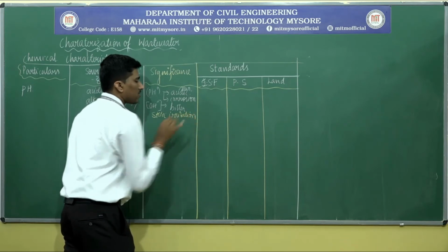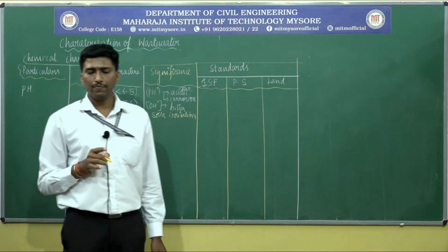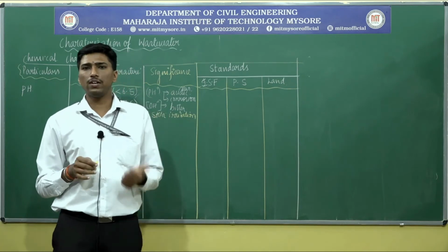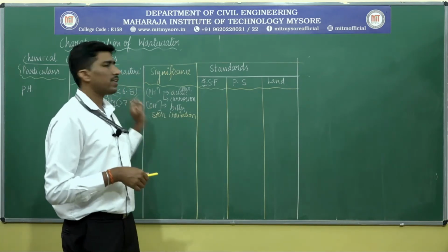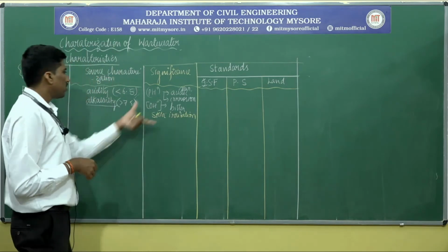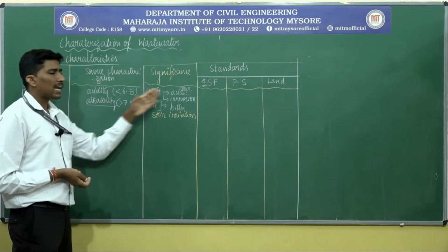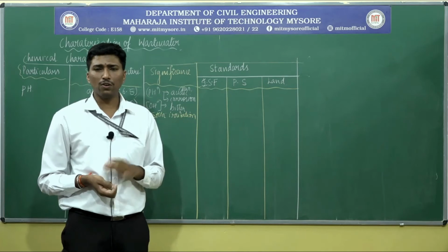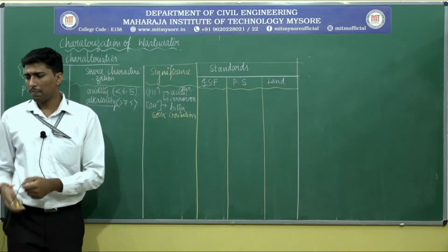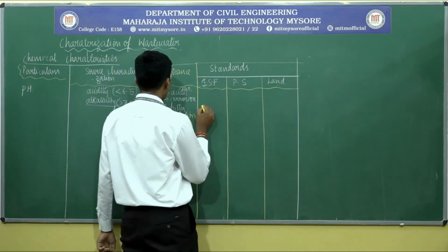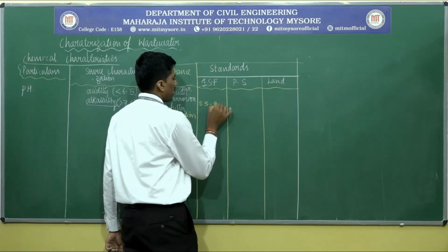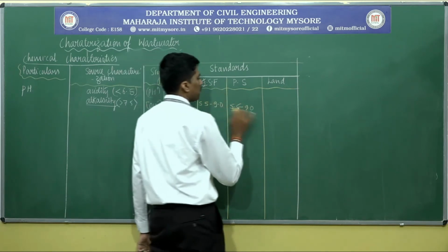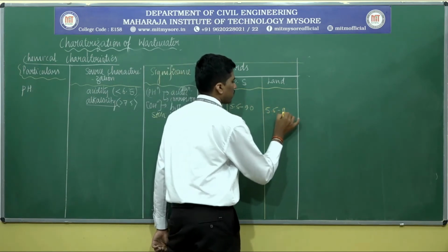You might have heard about the lake acidification process where fishes tend to die. Even in acid rain formation, if you check the pH of the rainwater, you can identify that it will always be less than 5. That is the reason we come across this. A highly alkaline condition is mainly due to industrial wastewater being mixed with domestic wastewater. Usually the domestic wastewater should possess a pH value from 5.5 to 9.0, for inland surface water, public sewers, and even for land.